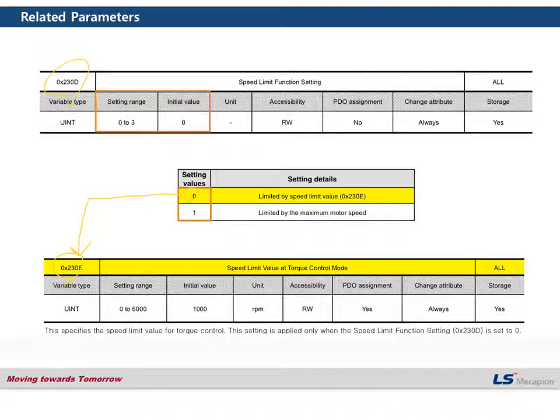The second way is to limit speed by the maximum motor speed. If you set the value of 1 for parameter 230D, in this case you don't have to set any certain value for the speed limit, because this is determined by the motor specification. By setting the motor ID, the maximum motor speed is determined based on the user's motor.